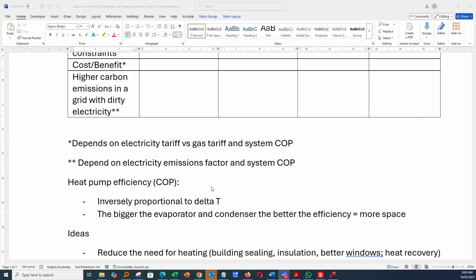Now, also, the bigger the evaporator and the condenser we can build, the lower the delta T we can get away with between the refrigerant on the inside of the evaporator, or the condenser in this case, and, let's say it's an air system, the air. With a bigger condenser and therefore a lower delta T, we can generate either more heat, or high temperature air if it's a furnace type situation, or we just need more space. So space constraints are the issue.